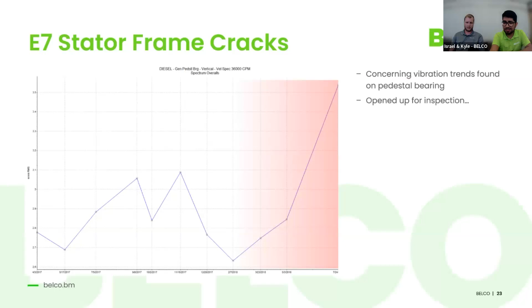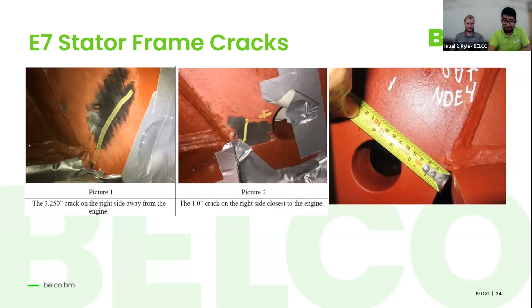So we open up the unit for inspection, and what do we find? We find quite a few cracks on the unit, on the stator frame. Usually you want your stator frame to be a pretty solid piece of equipment, right? You don't want these things falling apart and vibrating. So we had to carry out a metal stitching operation from this point.